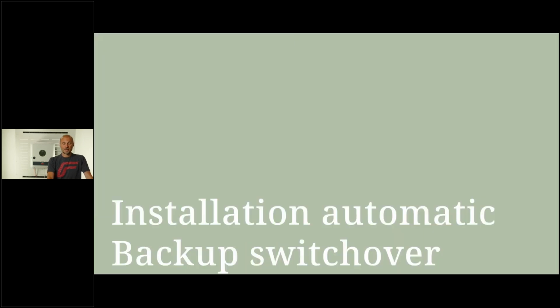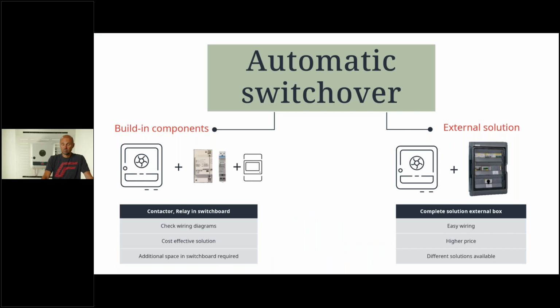Now to the installation of the automatic backup power switch over. Here we basically also have 2 solutions. The first is the components which we build in the switchboard. So you do the wiring of the contactor and the relay on your own. Therefore, you need, of course, to check the wiring diagrams to have the right ones. You also need additional space in your switchboard. That's sometimes a little bit tricky, but it is a cost-effective solution, and usually you don't need too much space in your switchboard. For a new house, of course, this would probably be the preferred solution.